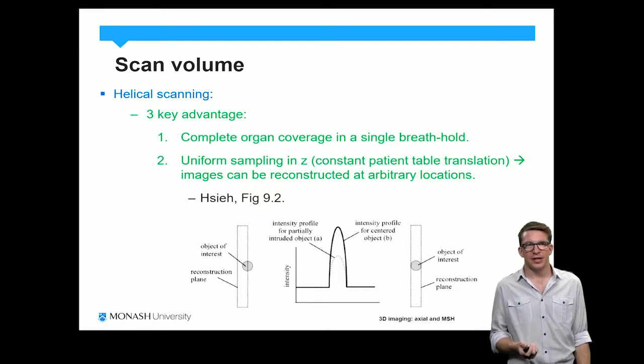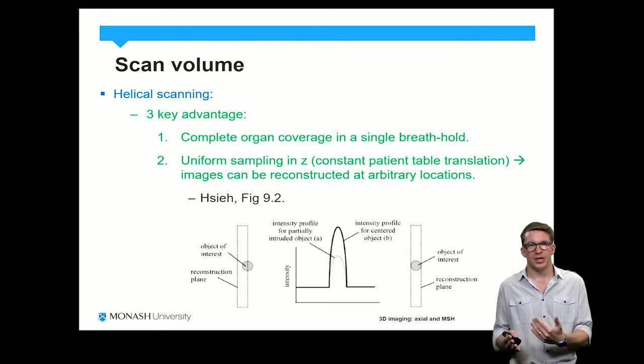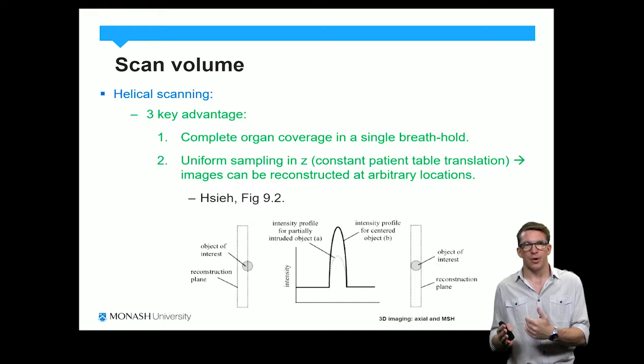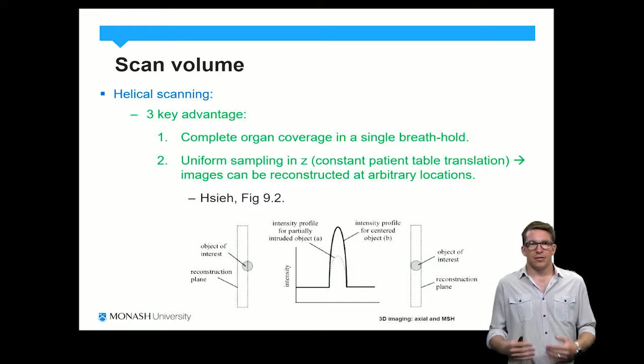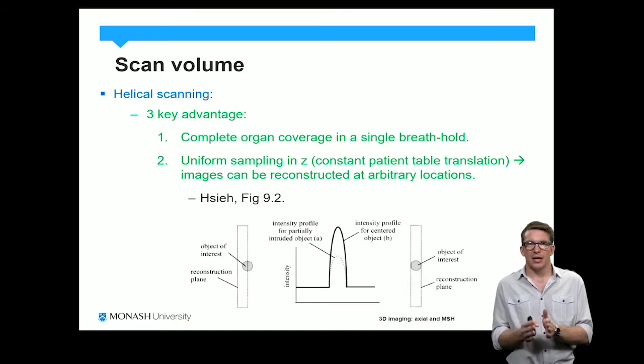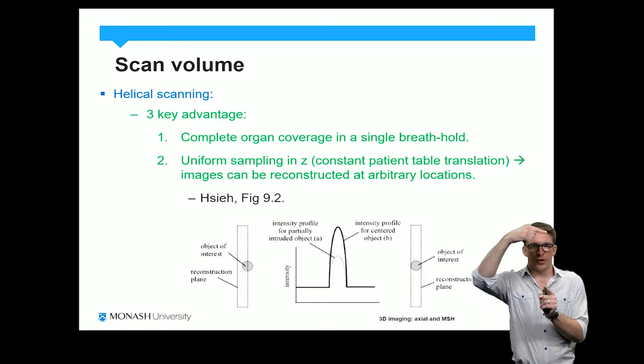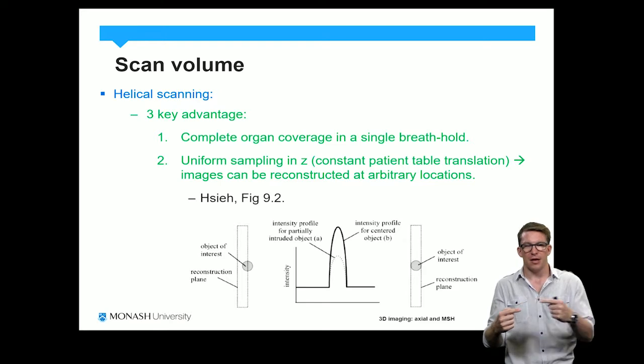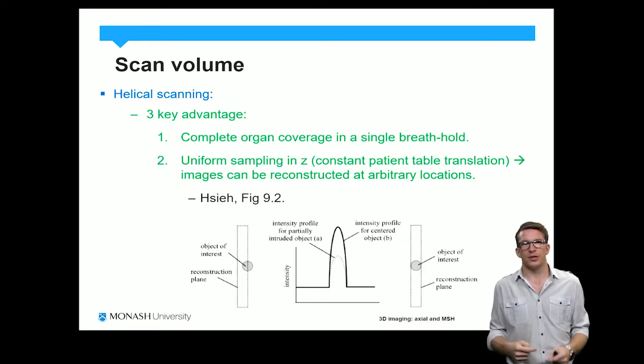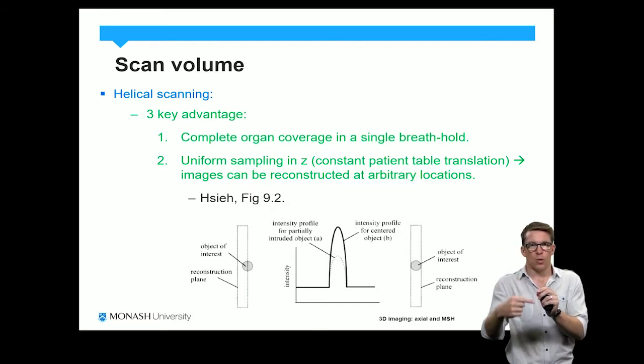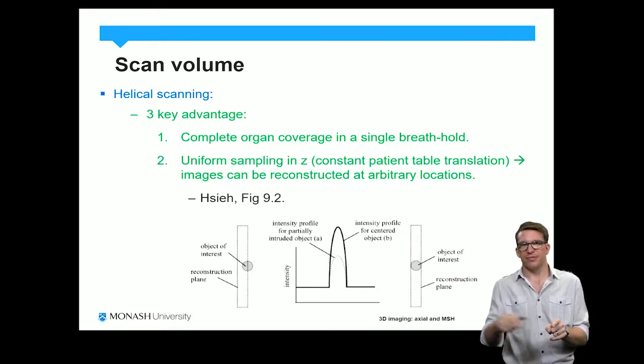There are three key advantages of helical scanning. The first is that we get complete organ coverage in a single breath hold because we can vary our pitch — something we clearly couldn't do in axial scanning mode. The increased sampling means that we can reconstruct slices at arbitrary locations. In axial scanning, at any given Z location we had all 360 degrees of data, but now because the patient bed is moving continuously while the scan is ongoing, we don't have all of our angular data at one Z but have some angular data at each Z — the data spread out on a theta versus Z plot.